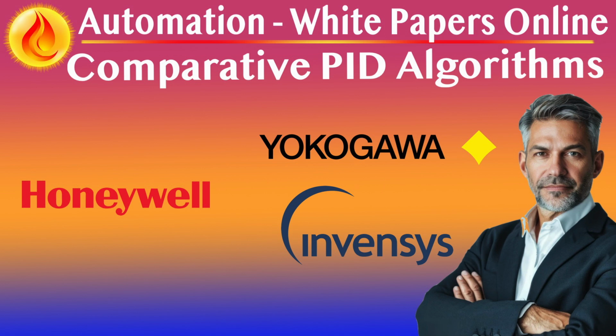Invensys, using series algorithms, applies derivative on error by default. This can cause overshoot and instability, particularly in setpoint-driven processes or fast-changing loops. While low-pass filters can be applied, they're often fixed or less user-configurable in legacy systems. In newer versions, filtering capabilities improve, but derivative filtering is still less transparent than in Yokogawa.